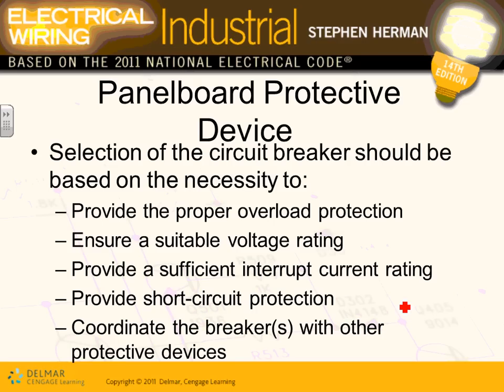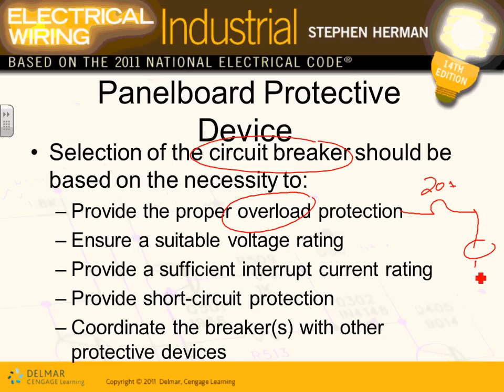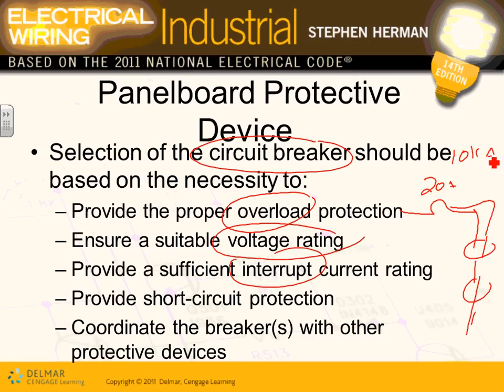How do you select the circuit breakers inside as a branch circuit or a feeder inside the panel? I have a 20 amp circuit breaker right here to provide overload protection for the circuit, so we can put our lights on this one, right? Ensure suitable voltage rating, so you don't want to have a lot of voltage drop in the circuit. Sufficient interrupting rating, so I'm going to make this one 10,000 amp to interrupt the short circuit, 10,000 amp. Provide the short circuit protection, which is part of my sufficient interrupting rating.